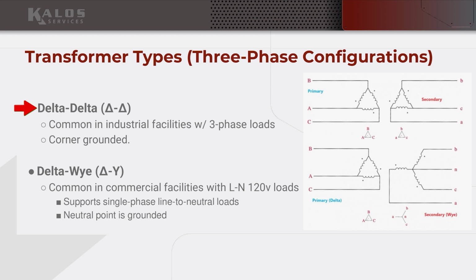And so we won't see a delta configuration in commercial applications with a lot of 120 volt loads. This is going to be more the industrial side of things, and also power distribution systems. Utility side distribution systems will use delta a lot because they don't need the neutral as frequently on those systems. Delta-wye, this is a configuration we will see very frequently, because what we're mostly doing are projects that have a good distribution of both three-phase loads as well as 120 volt line to neutral loads. So delta-wye is going to be the configuration.